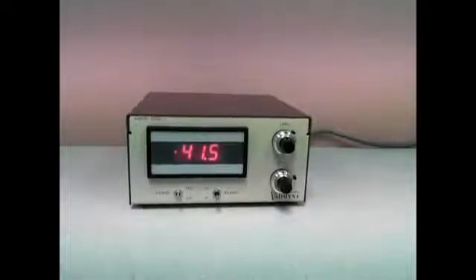Now tap the zero and span adjustment knobs to see if the signal jumps. It is normal for the display to change slightly with tapping, but a change of several percent may indicate worn potentiometers.